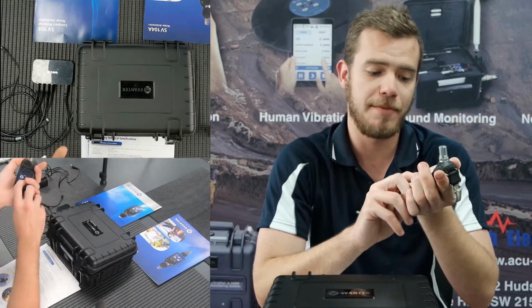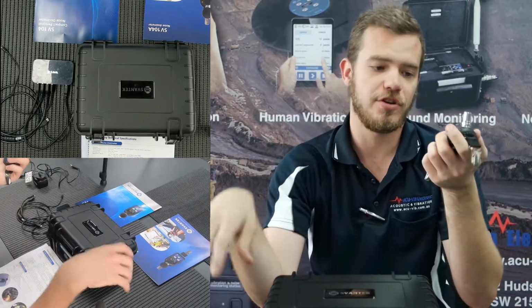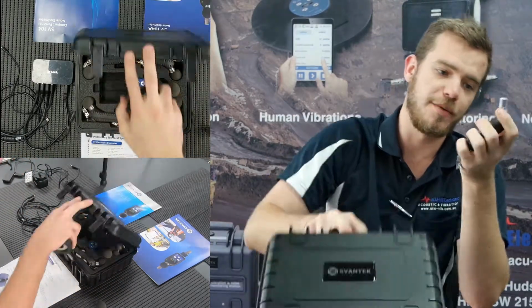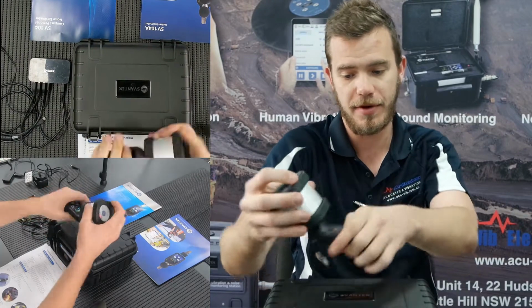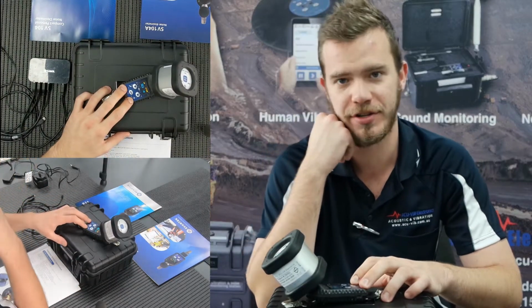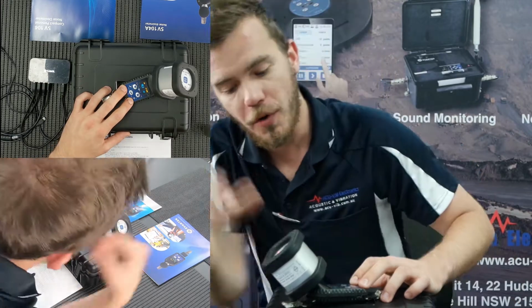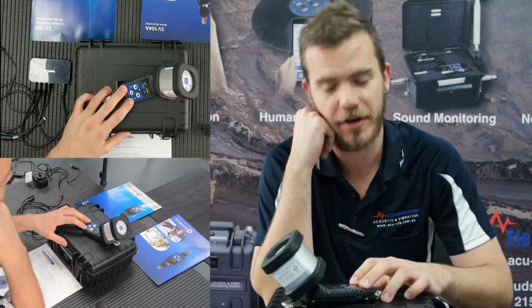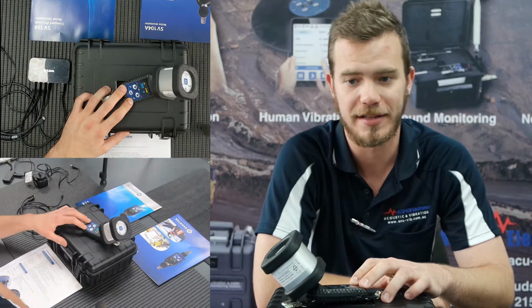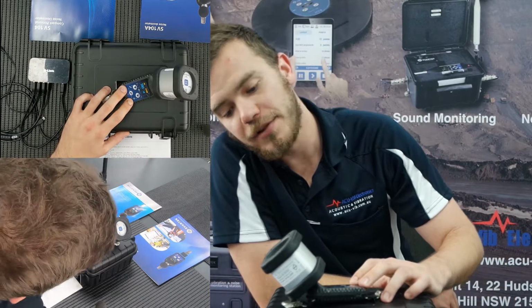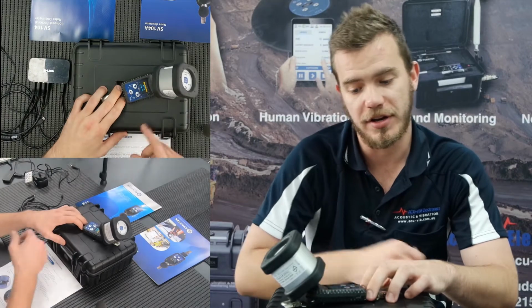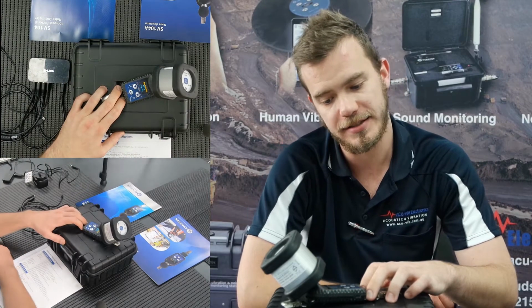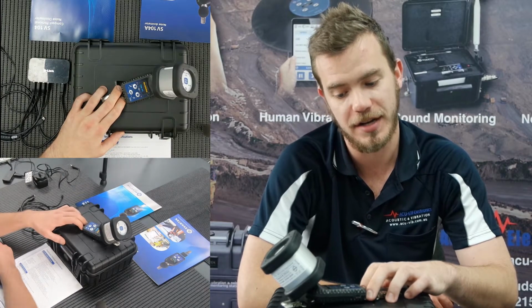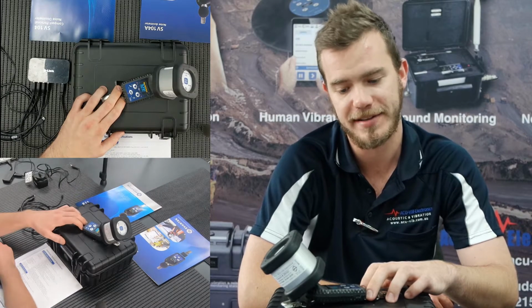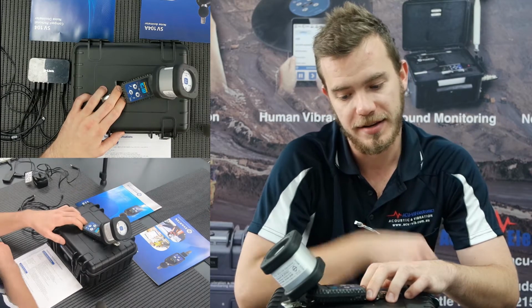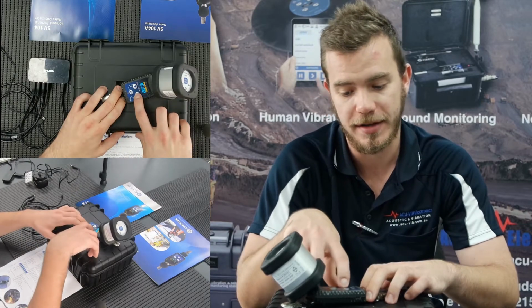So just to prove the MEMS microphone drift, I'm going to show you quickly how I can prove this. So basically I'm going to pop on an acoustic calibrator, and I'm going to show you how to do a calibration in just a few moments. Though while I'm on the subject of the MEMS microphone, just to prove its robustness and its durability when it's in the field. So basically once a level has been sensed, the unit itself is going to go through its auto calibration. It's going to count down, it's going to give us a calibration factor which shouldn't be more than 0.5 dB. If it is, we have to disregard the results. That's by the standards. So we have a 0.04 dB C factor.